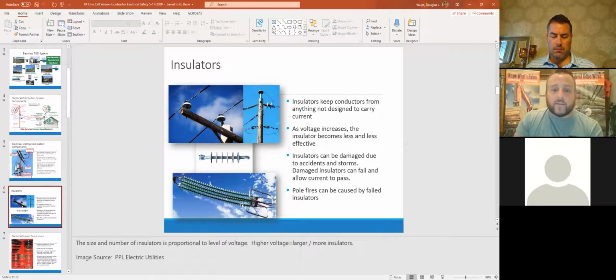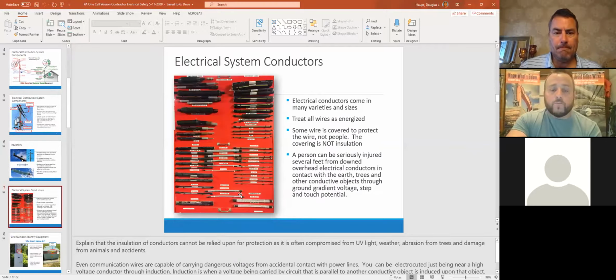And then the big one down here on the bottom, this is actually an insulator string for a 500,000 volt transmission line. You'll see this is quad bundled. Each one of these strings is about 28 feet in length on a 500 kV line. So pretty long, and obviously it takes a lot of insulation to stop that amount of voltage coming into a pole.